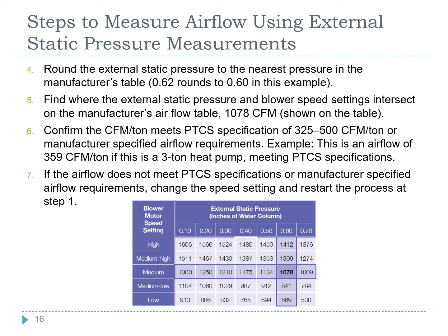Next, we're going to round the external static pressure to the nearest pressure in the manufacturer's table. In this example, 0.62 would round down to 0.60. Find where the external static pressure and blower speed setting intersect on the manufacturer's airflow table. 1078 CFM is shown here.